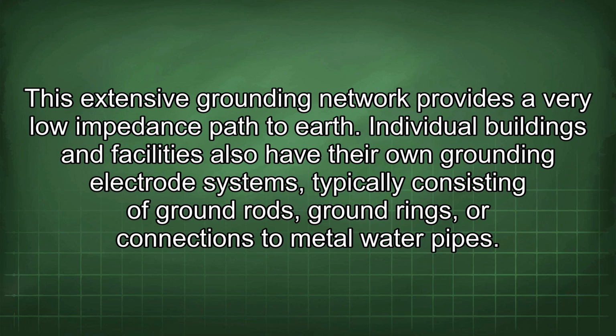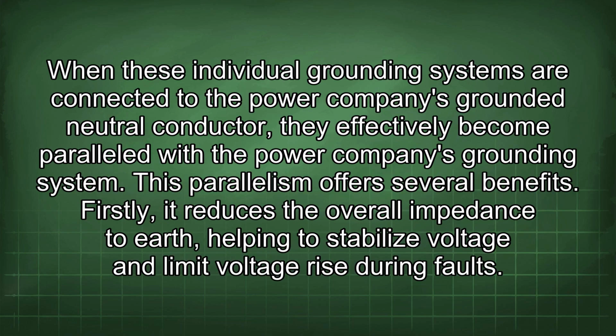Individual buildings and facilities also have their own grounding electrode systems, typically consisting of ground rods, ground rings, or connections to metal water pipes. When these individual grounding systems are connected to the power company's grounded neutral conductor, they effectively become paralleled with the power company's grounding system. This parallelism offers several benefits.